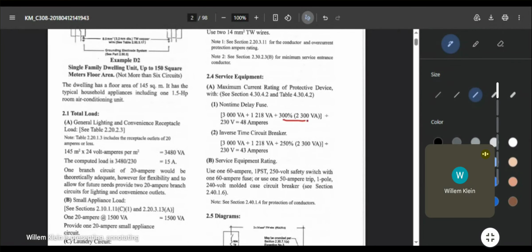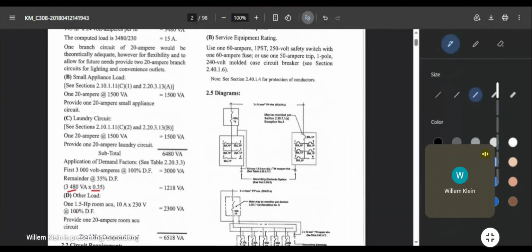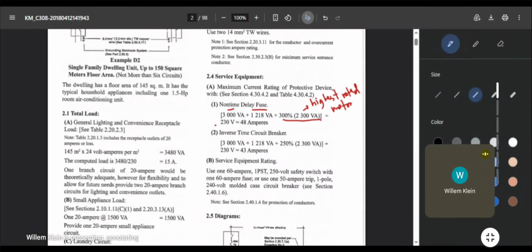And then plus this part, the 300% times this one for non-time delay fuse. So we're computing for the fuse. You use a 300% multiplier, and then you will get your highest rated motor. In this case, your only motor in this circuit is your aircon, the 1.5 HP room air conditioning unit. That's your only motor anyway, so you will use that. But in the event that you have multiple aircon, for example two 1.5 HP, one 1 HP, or a 2 HP aircon, let's say your living room has air conditioning on its own, wow, okay, rich kid, you will select whichever is the highest rated among those, and you will use it here. Okay. So question, what about the other aircon po?